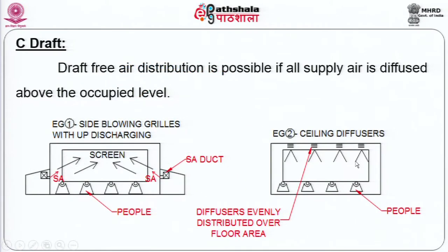Now, looking at what we had, supply air grills and ceiling diffusers, these two slides show you how they can be used. In the first slide that you see here, you have a sidewall grill. To make it draft free, you will notice that air is ideally discharged upward so that it does not reach the occupants directly at all. In the diffuser, it automatically takes place. The air is discharged parallel to the ceiling and virtually you have no draft in the occupied area.